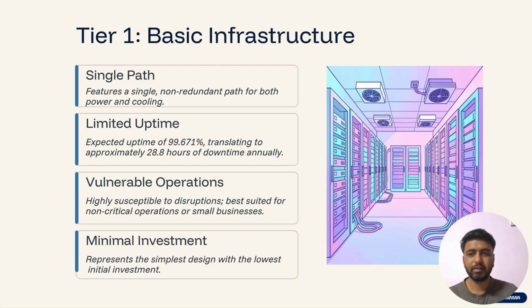Now let's talk about tier 1. Tier 1 is like a basic scooter. It has one power path and one cooling path, with no backup components. This means if your main source fails, there is no redundancy to cater to that IT load. So the expected uptime is around 99.671%, meaning around 28.8 hours of downtime per year. Tier 1 data centers are best for small businesses and non-critical IT rooms.